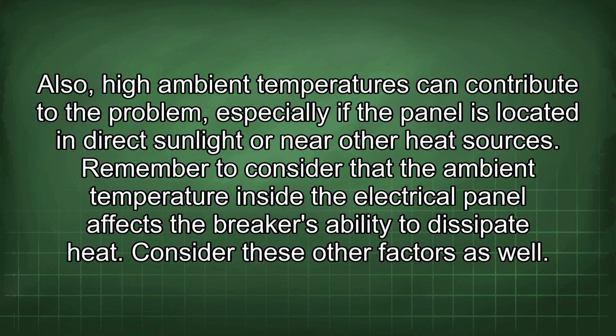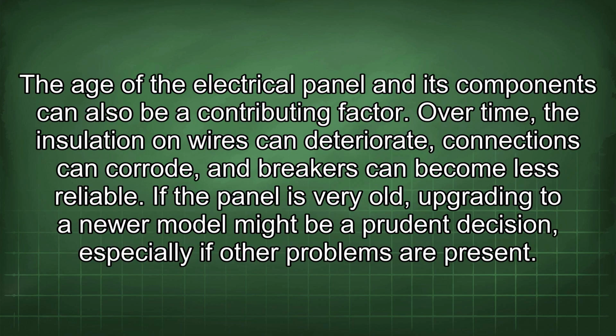Also, high ambient temperatures can contribute to the problem, especially if the panel is located in direct sunlight or near other heat sources. Remember to consider that the ambient temperature inside the electrical panel affects the breaker's ability to dissipate heat. Consider these other factors as well. The age of the electrical panel and its components can also be a contributing factor. Over time, the insulation on wires can deteriorate, connections can corrode, and breakers can become less reliable.